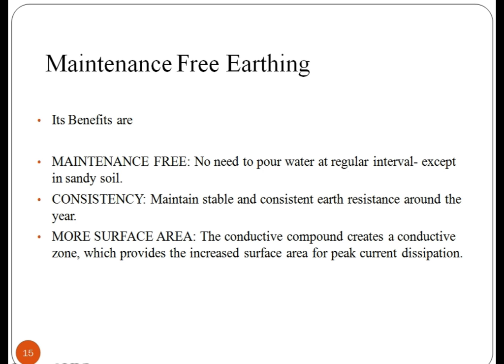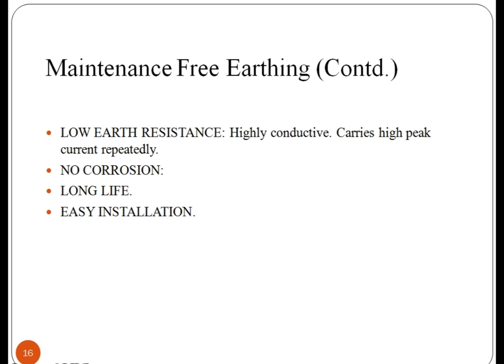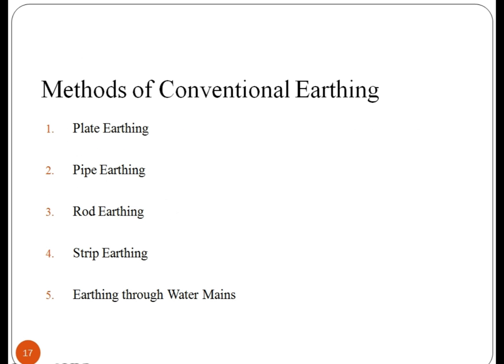Some benefits of this earthing are: the conductive compound creates a conductive zone which provides increased surface area for peak current dissipation, and also gives a stable reference point. It maintains stable and consistent earth resistance around the year. Some other benefits are no corrosion, long life, and easy installation. Now, let us look at the methods of conventional earthing, and these are plate earthing, pipe earthing, rod earthing, strip earthing, and earthing through water mains.